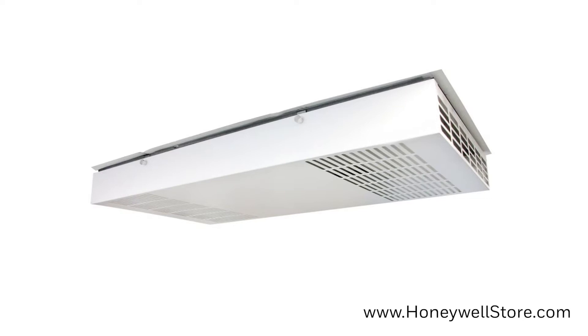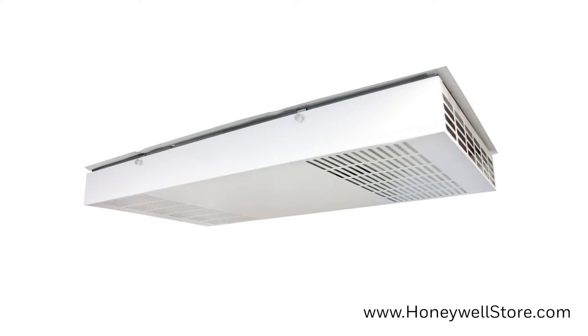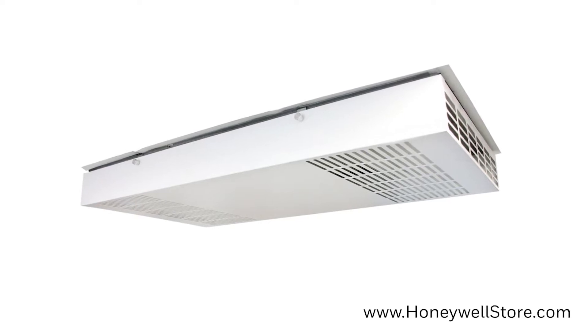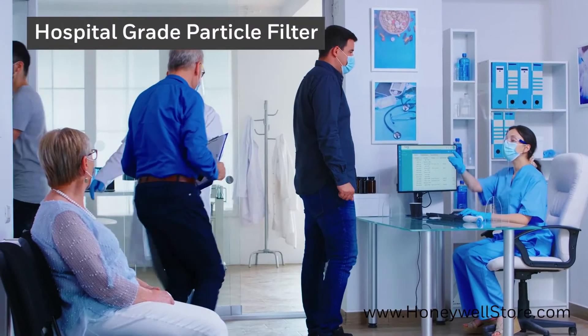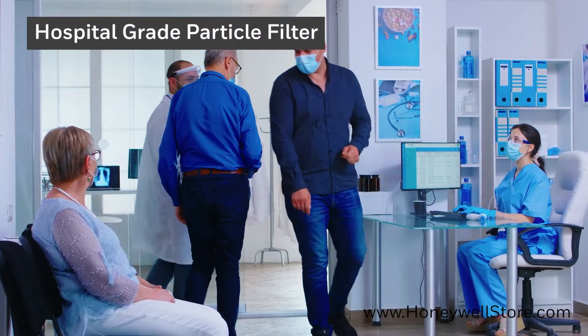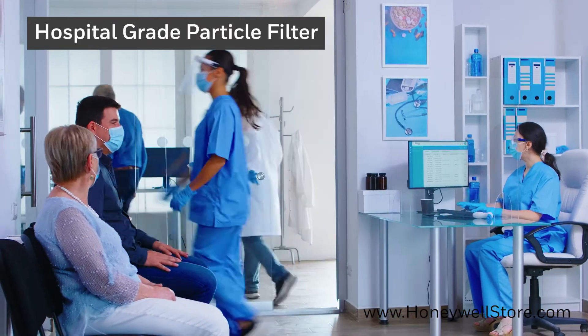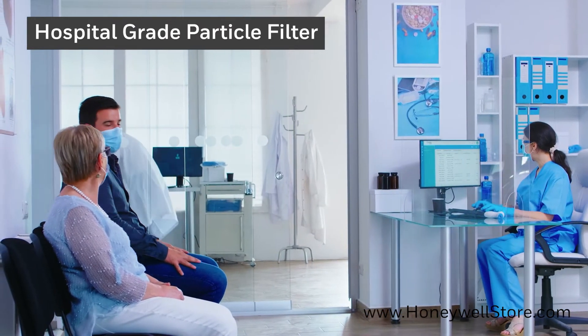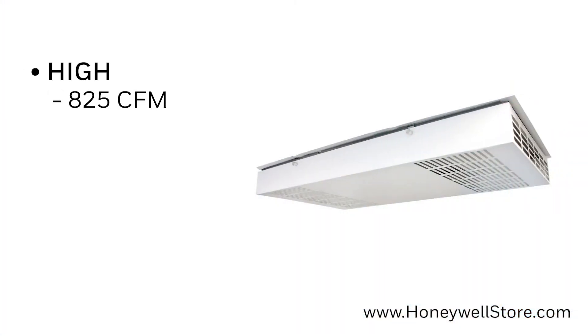The Honeywell ceiling-mounted commercial media air cleaner with HEPA filters was designed to overcome the increase in airflow resistance normally caused by filter loading. This media air cleaner comes with a high-efficiency particulate air filter that is 99.97% efficient at capturing particles at 0.3 microns or larger from the air that passes through the filter.